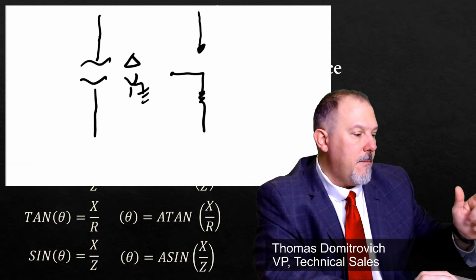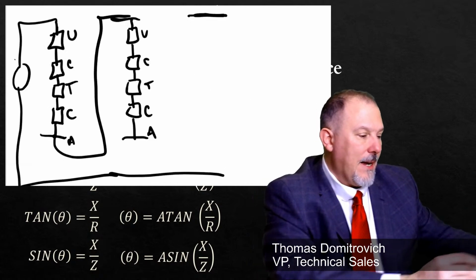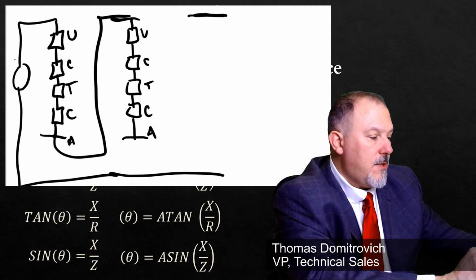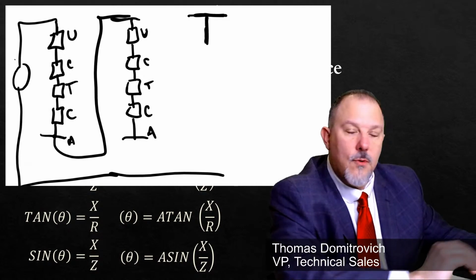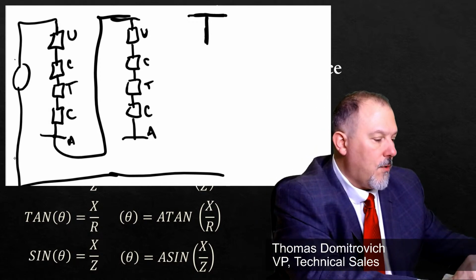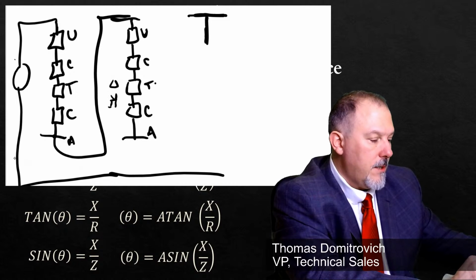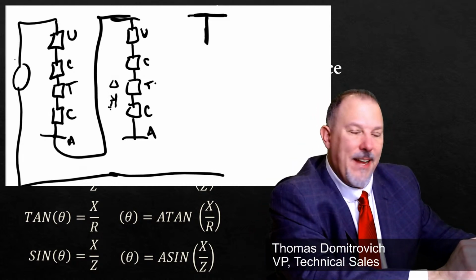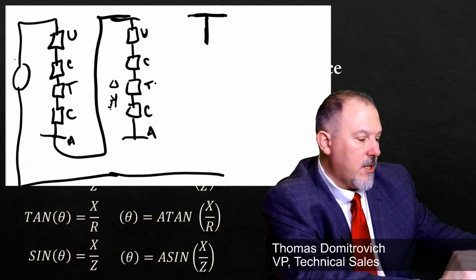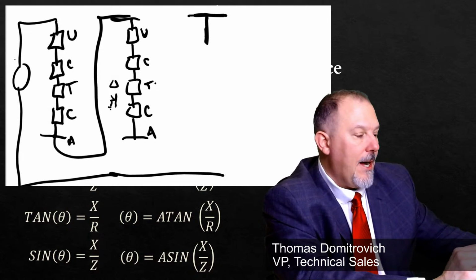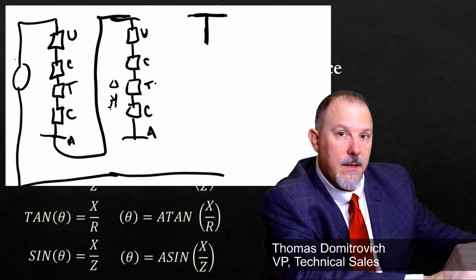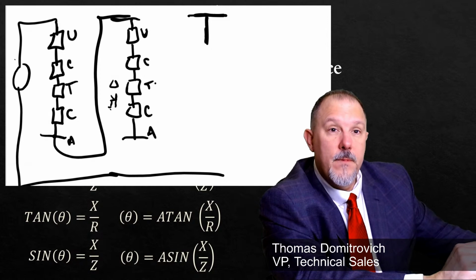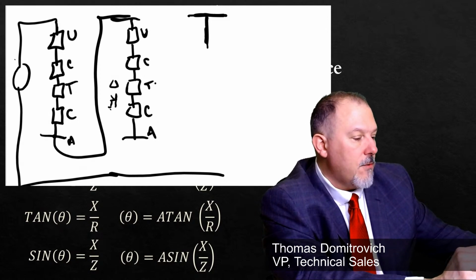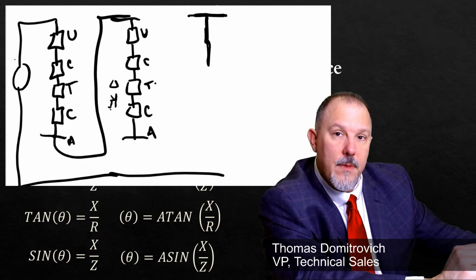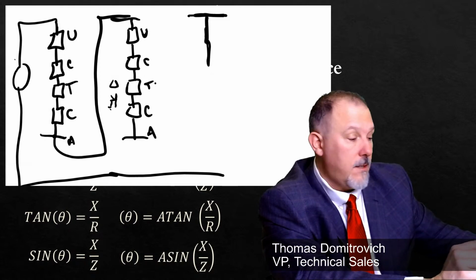So if I look at my impedance diagram, this is my utility. I don't include my utility, because why? This transformer here is a delta Y grounded. I won't have any ground fault currents flowing because of my fault on the secondary, bus A. I won't have any ground fault current flowing through that utility. It's not a part of my zero sequence circuit. I won't have any fault current flowing through that conductor. That's not a part of my zero sequence circuit.